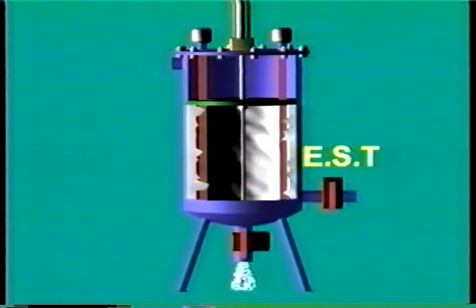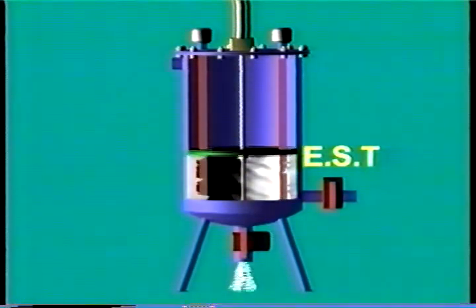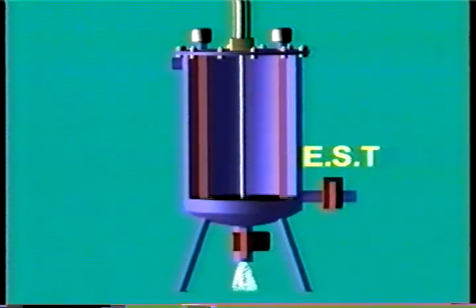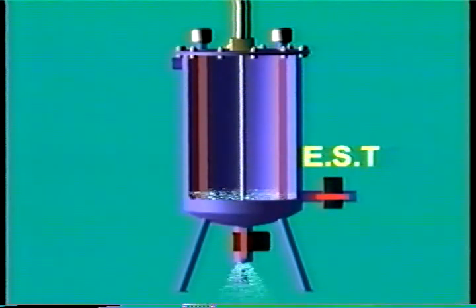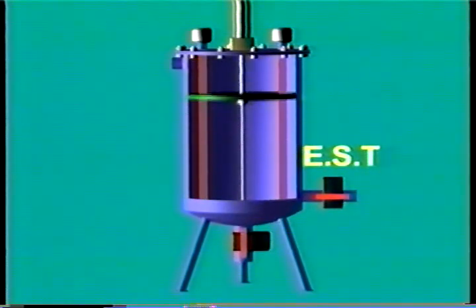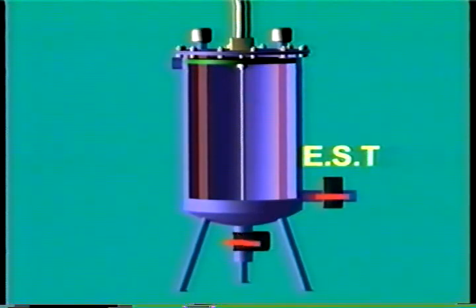The piston-actuated scale wiper then moves downward, removing the scale from the chamber wall and flushing it down the drain. The inlet valve is then opened again, and the chamber is rinsed, the drainage valve is closed, the wiper returns to its place, and the system is ready to resume the electrolysis operation.